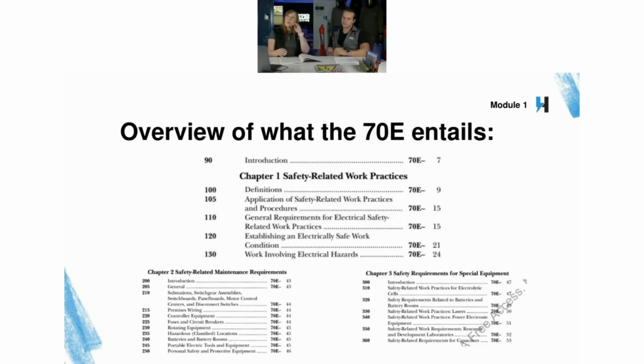Okay, so we've gotten to the point where most people are pretty familiar. You know where to shut it off, apply your lockout tagout devices, bleed off the energy. But then what? The most important part is to use that adequately rated portable test instrument to test for absence of voltage. There is a change in the verbiage for the 2024 edition for that specific step, and we'll talk about that later. But that's a very important step. And then, of course, if there's a need, induced voltage or stored electrical energy, sorry, that's the term stored, then apply your temporary protective grounding equipment. Okay, so those are the steps. That's what Article 120 is dedicated to, explaining all of that detail.